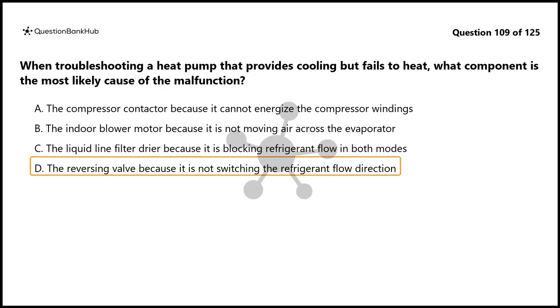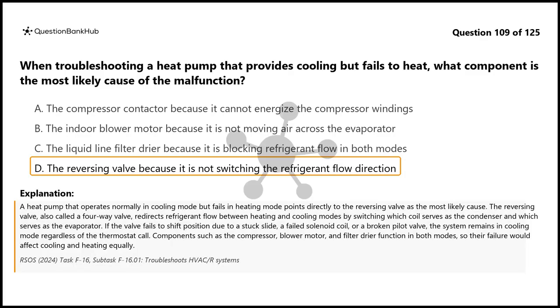The correct answer is D. A heat pump that operates normally in cooling mode but fails in heating mode points directly to the reversing valve as the most likely cause. The reversing valve, also called a four-way valve, redirects refrigerant flow between heating and cooling modes by switching which coil serves as the condenser and which serves as the evaporator.